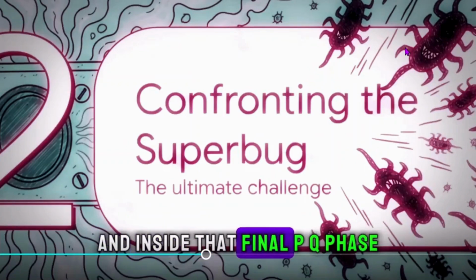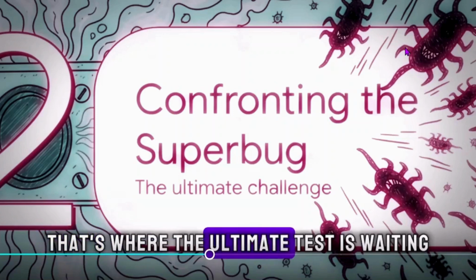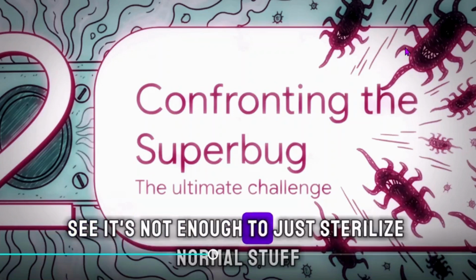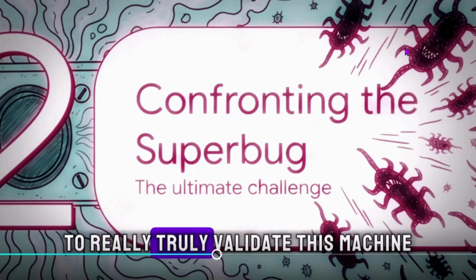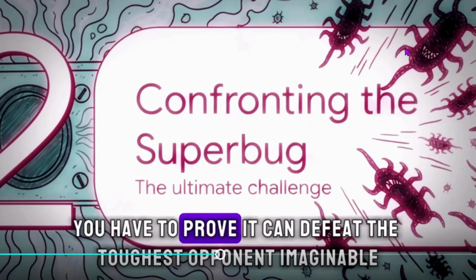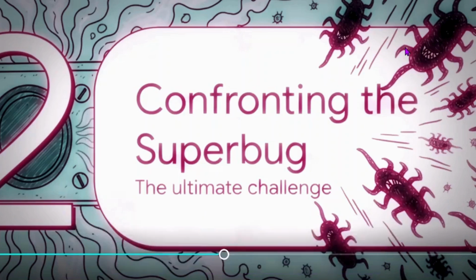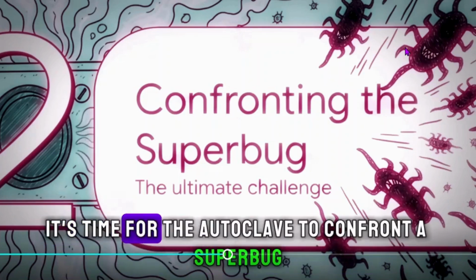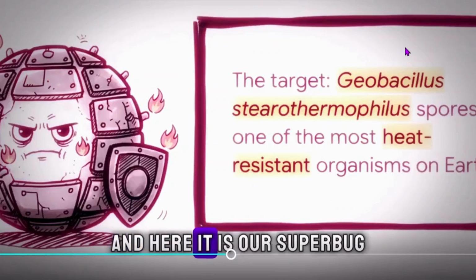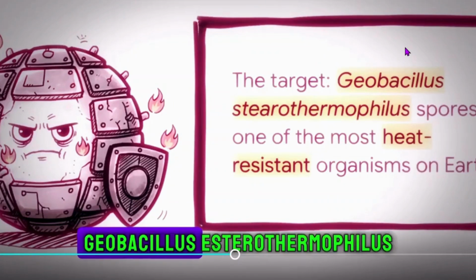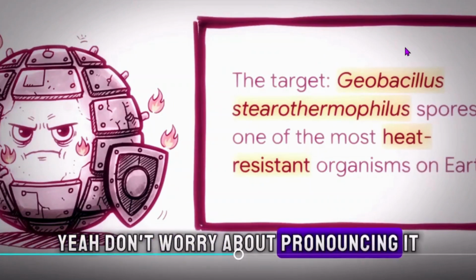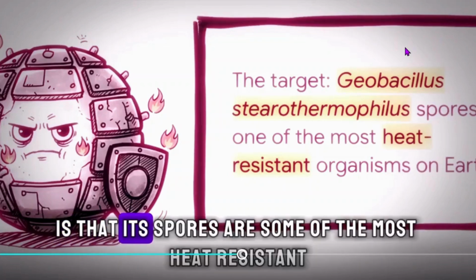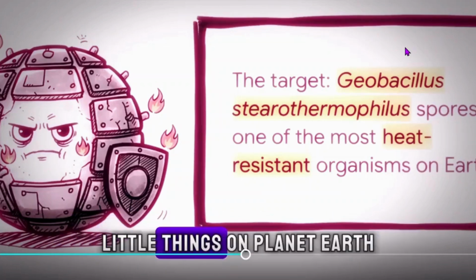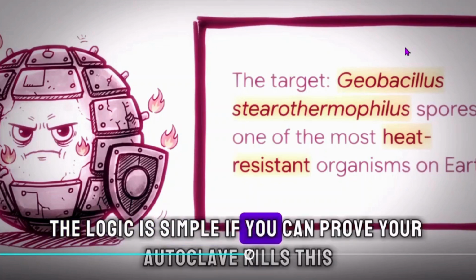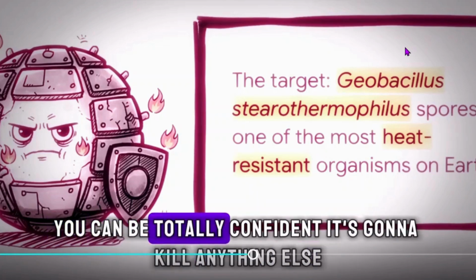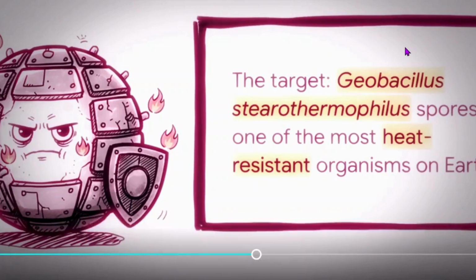And inside that final PQ phase, that's where the ultimate test is waiting. See, it's not enough to just sterilize normal stuff. To really truly validate this machine, you have to prove it can defeat the toughest opponent imaginable. It's kind of like the final boss battle. It's time for the autoclave to confront a superbug. And here it is, our superbug, Geobacillus stearothermophilus. Yeah, don't worry about pronouncing it. All you need to know is that its spores are some of the most heat-resistant little things on planet Earth. The logic is simple. If you can prove your autoclave kills this, you can be totally confident it's going to kill anything else.